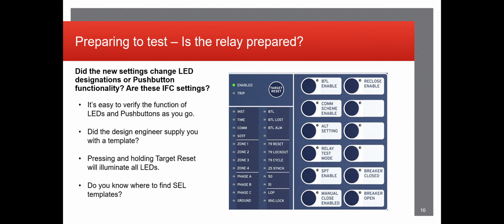Is the relay prepped? Did the new settings change LED designations or push button functionality? Are these issued for construction settings? The LEDs and push buttons are client dependent. Some of them actually don't even utilize the push buttons specifically. The LEDs are very common, especially to show what kind of trip occurred, whether it be a zone 1 trip or a differential or a lockout or a phase differential, anything like that.